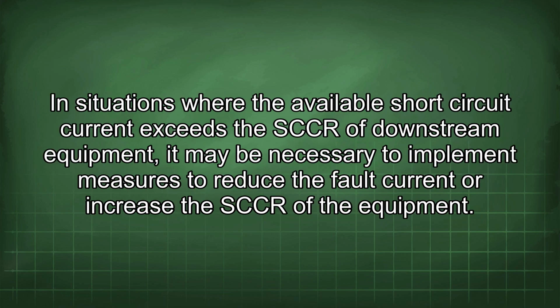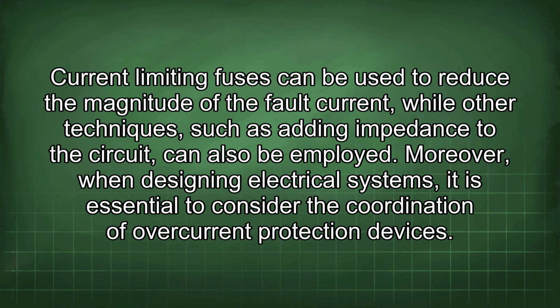In situations where the available short-circuit current exceeds the SCCR of downstream equipment, it may be necessary to implement measures to reduce the fault current or increase the SCCR of the equipment. Current-limiting fuses can be used to reduce the magnitude of the fault current, while other techniques, such as adding impedance to the circuit, can also be employed.